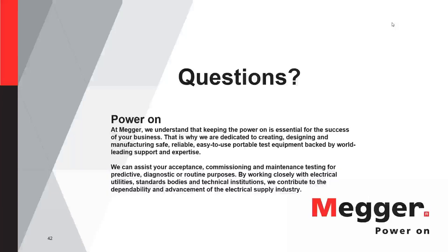But really, it comes down to the fact that the oil obviously is there in the fault case, whereas there is air in the fault case for the solid dielectric cables. And that really makes the difference in the breakdown voltage because you have oil versus air. And there are some differences in oil also. But the differences that Robert was talking about, EPR cable, they didn't relate to the difference in breakdown voltages. They purely related to the electric or dielectric properties that affect the TDR pictures, okay? And the attenuation and dispersion and also dielectric losses, okay? But it has nothing to do with the breakdown voltage between those two types of solid dielectric insulation.